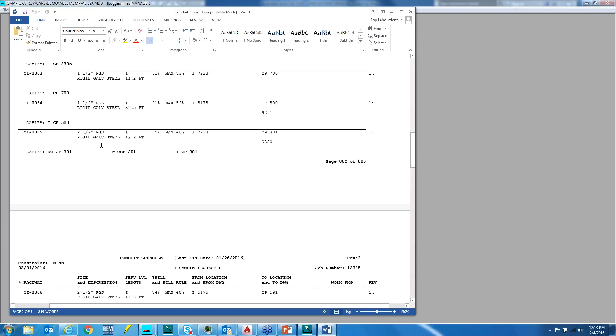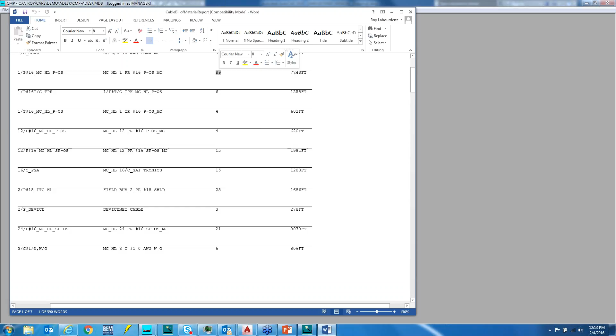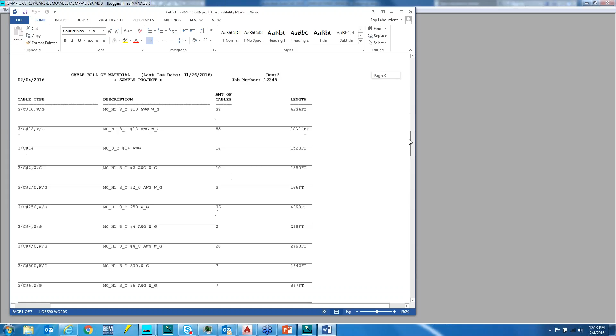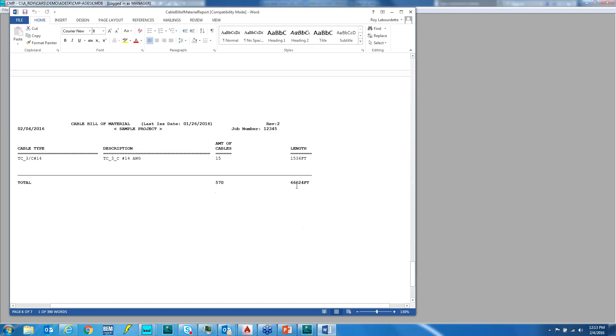Next one I'll do is a material report on cable, and I'm going to go ahead and create that report. It's asking me if I want to refresh my conduit and cable, and I don't, because I just rerouted all these cables, so I know that my data is current and accurate. What this is telling me is that I have a single pair number 16. I've used it 89 times for a total length of 7,700 feet. And you can see all of the cables that are taken off, and that program just routed 66,000 feet of cable and did the cable takeoff.